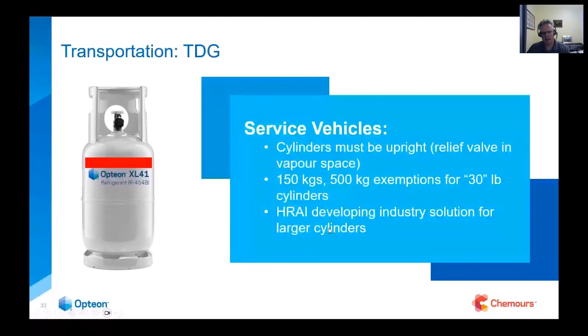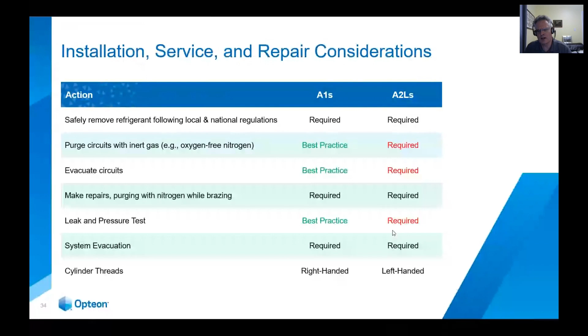Installation and service. So servicing equipment, what's different? And the reality is a lot of it's the same. We just need to do what we've been trained to do in college or in trade school. You really need to make sure that circuits are purged with an inert gas, nitrogen. It's really been a best practice, but you really have to do it. You have to evacuate circuits, and you have to leak test and pressure test systems. This is something we've been doing already, but certainly these are some of the things we must, without a doubt, do as we transition to A2Ls.